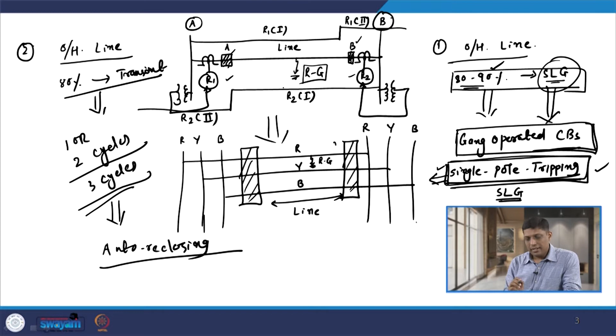Again let us consider the same example, say an R-G fault occurs. So, both relays R1 and R2 detect this fault and give a signal to the respective breakers at substations A and B, and both breakers will operate. Now, in case of an RG fault, if the breaker becomes open and after some time delay we again reclose the breaker, both the breakers from bus A and bus B, then if these faults are transient in nature, they will automatically die down.